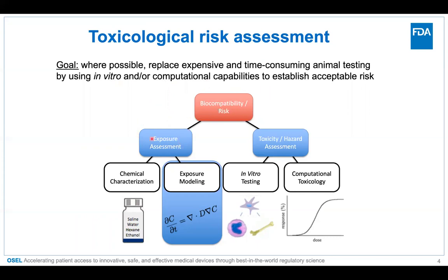There are two primary components of biocompatibility evaluation. The first is exposure — if we implant a device in someone, how much of some additive or contaminant in the polymer will come out and enter the patient. The other component is toxicity — how bad it is per unit mass. I'm focused on exposure assessment today, which you can do in vitro using chemical characterization, placing the device into a solvent and characterizing what extractables come out.